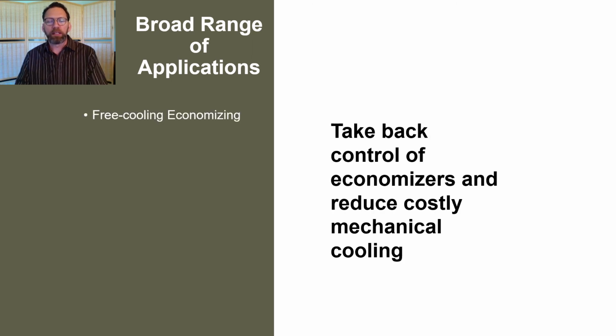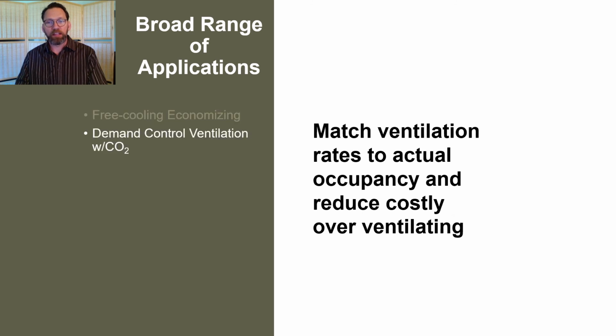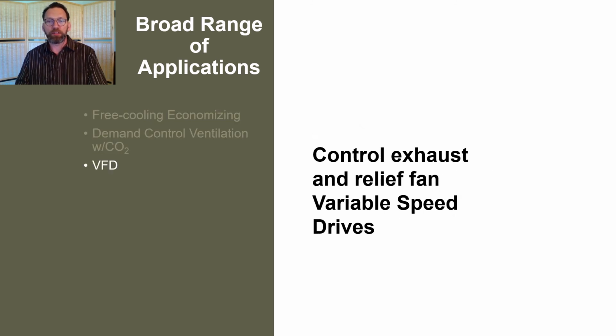Smart thermostats can control more than just rooftop units—there's a broad range of applications they can control. As I mentioned, the actuator motor for free cooling economizer is a good one, but also demand control ventilation with CO2 sensing, and variable frequency drives for exhaust and relief fans.